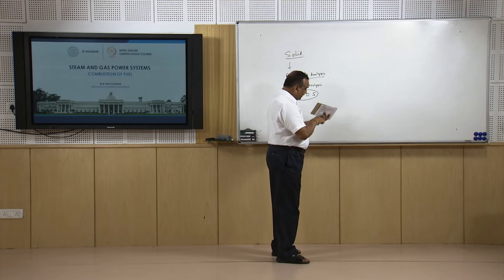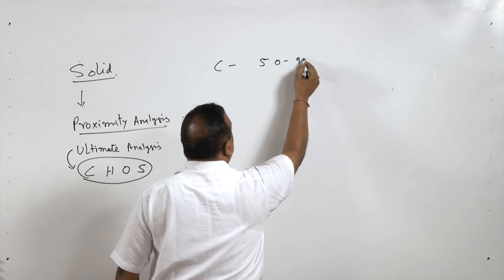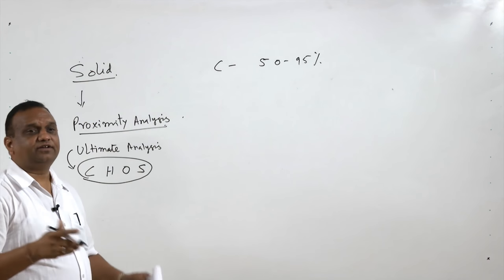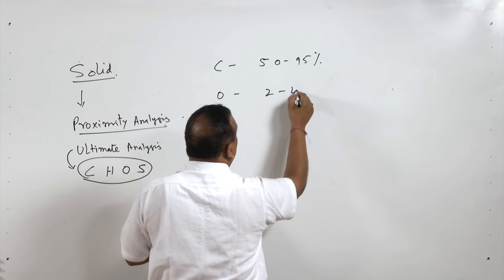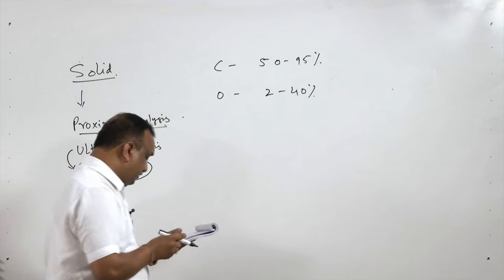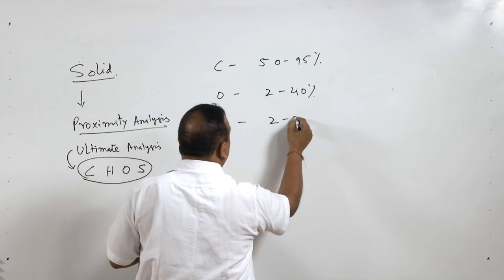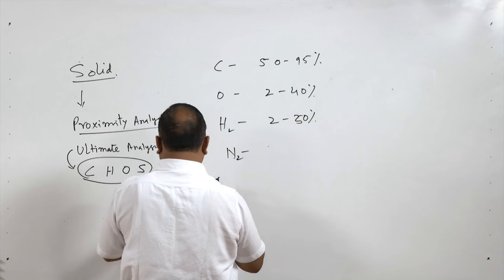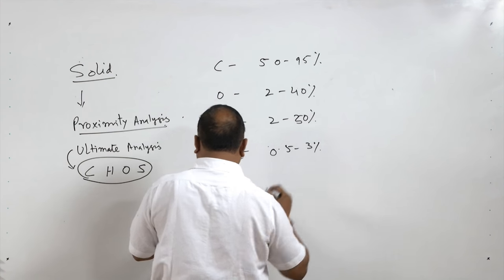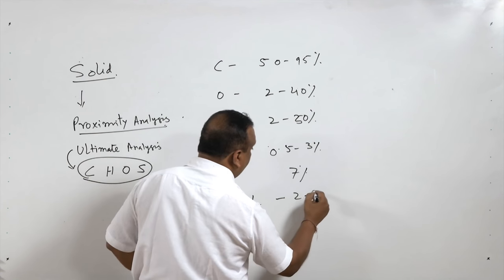Some typical figures: carbon can vary from 50 to 95 percent in coal — anthracite can go up to 95 percent. Oxygen can vary from 2 to 40 percent; peat coal can go up to 40 percent. Hydrogen can be 2 to 30 percent. Nitrogen is 0.5 to 3 percent. Sulfur can be up to 7 percent, and ash can range from 2 to 30 percent.